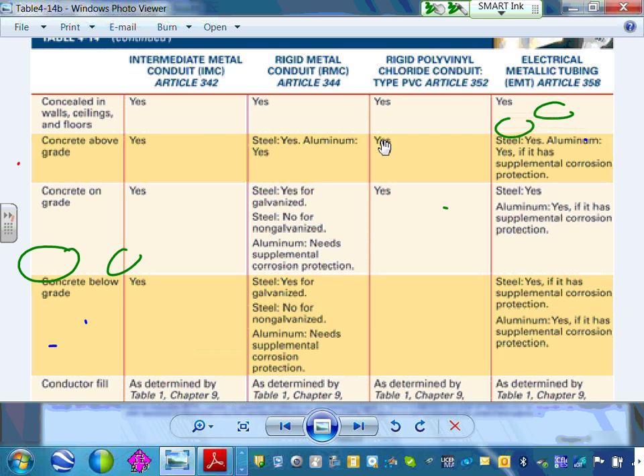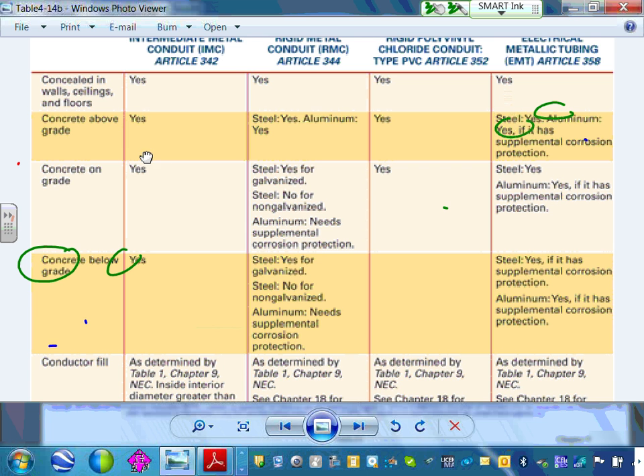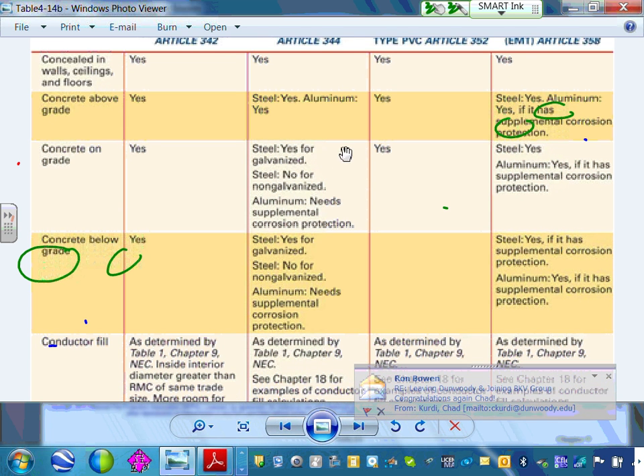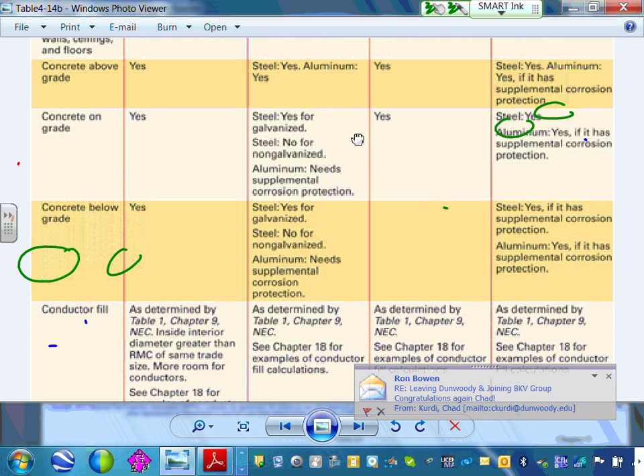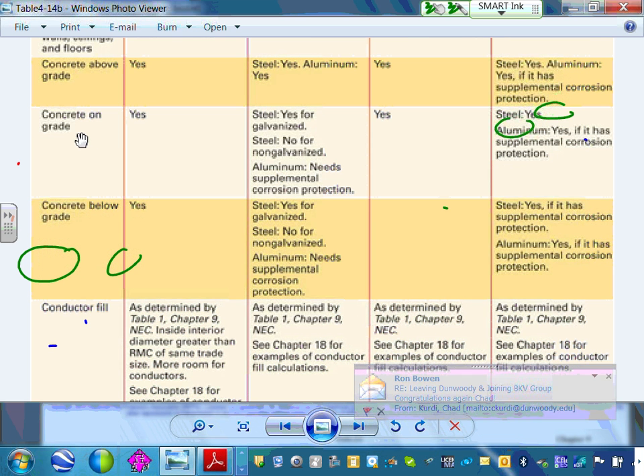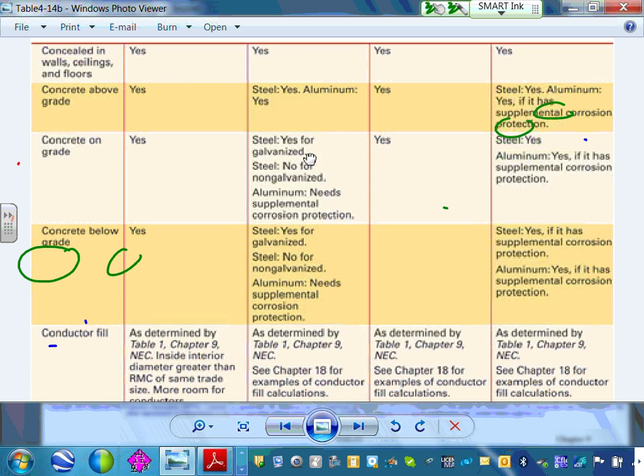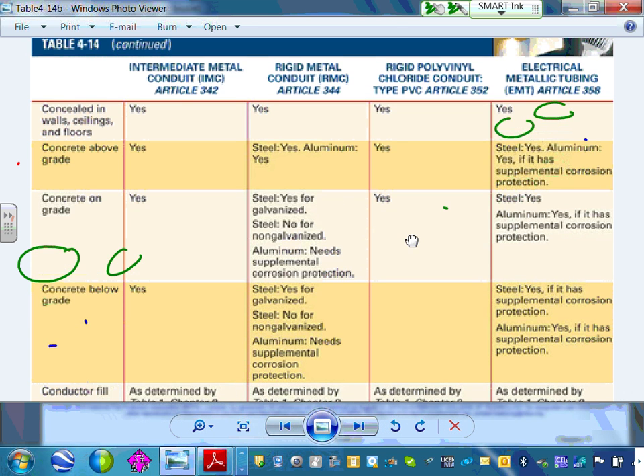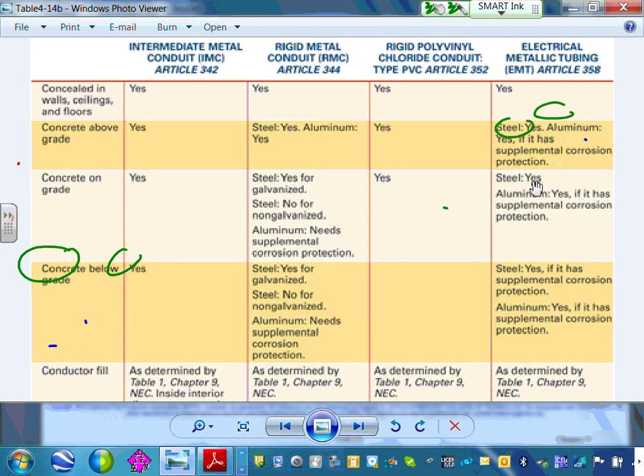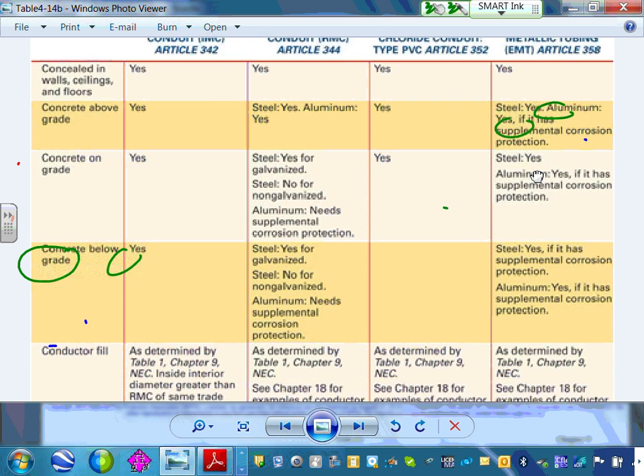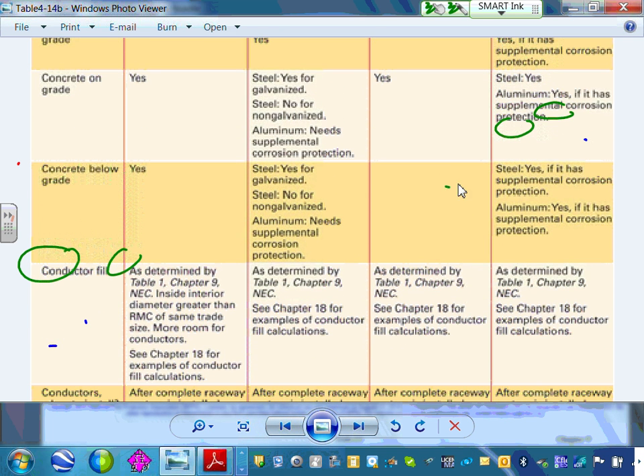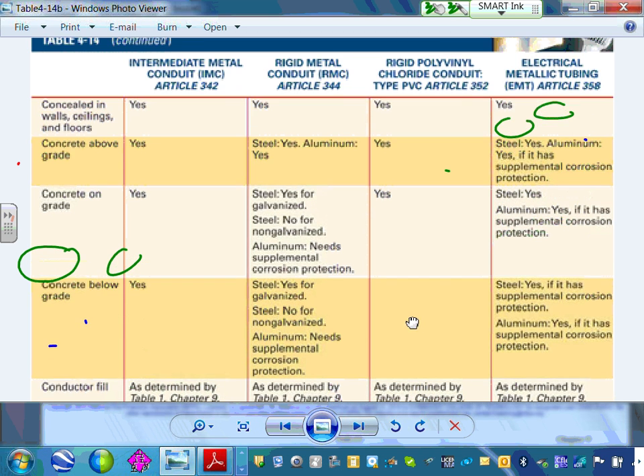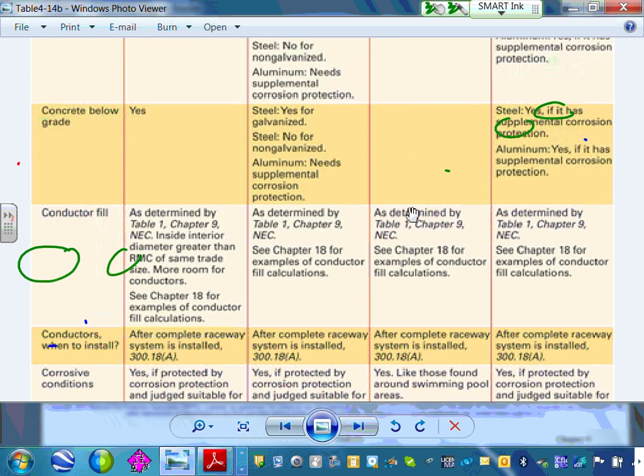Concealed in walls, can you conceal them? Bring it on, all of them. Concrete above, can you put them above grade? Bring it on. Concrete on grade, bury them basically. Yes, rigid PVC, yes for galvanized. Look at the EMT, can you even bury the EMT? Yes, but it's not your conduit of choice for burial though. Concrete below grade, your conduit of choice becomes PVC below grade.